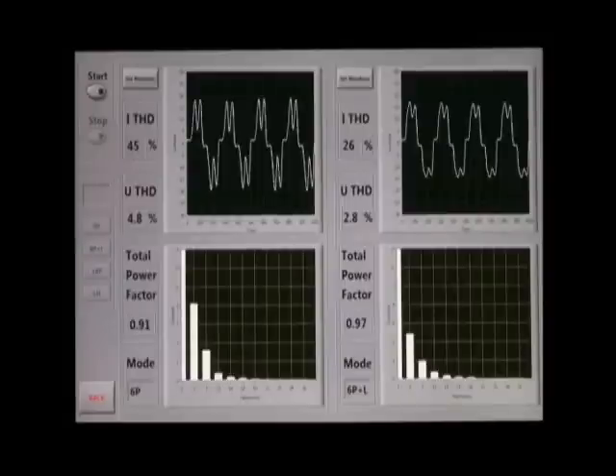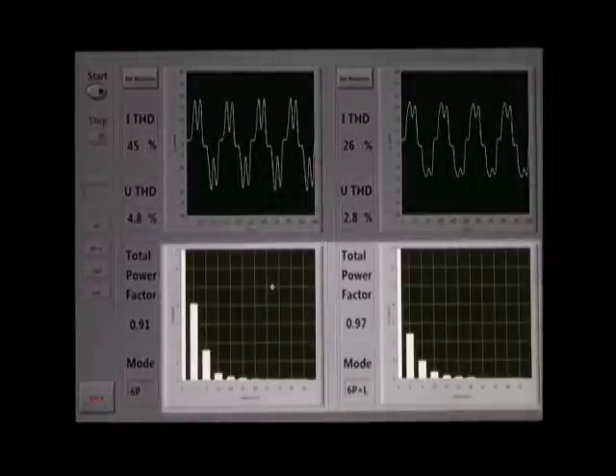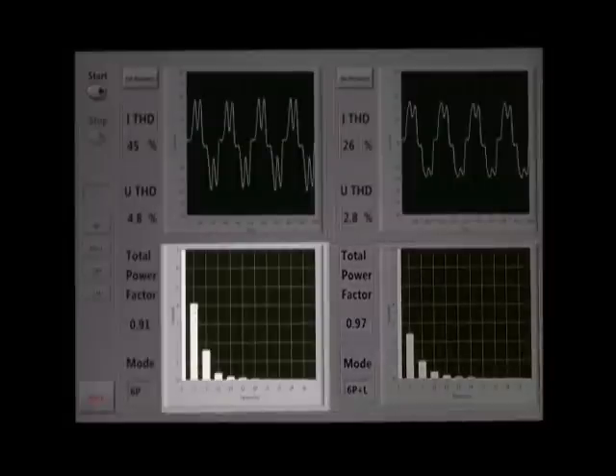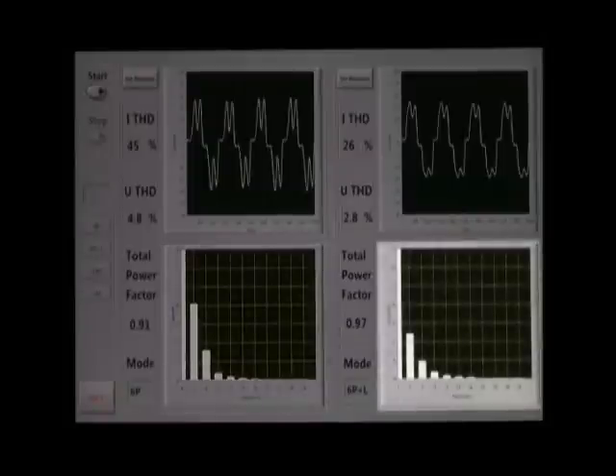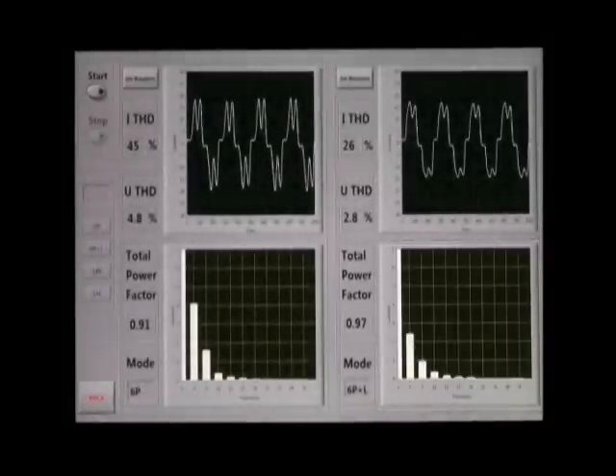Looking at these voltage harmonics, current harmonics, and power factors, it's also easy to see that adding an inductor is a superior form of harmonic mitigation to simply the 6-pulse by itself. On the lower graph, what I'd like to point out are the actual levels of the individual harmonics. These are laid out as 5th, 7th, 11th, 13th, etc. in terms of harmonics. And you'll notice the amplitude of each of these harmonic levels. The 5th harmonic and 7th harmonic on the 6-pulse are dramatically larger than they are when an inductor is also used. We'll see this change even more dramatically when we compare the 6-pulse with inductor to the 18-pulse solution.